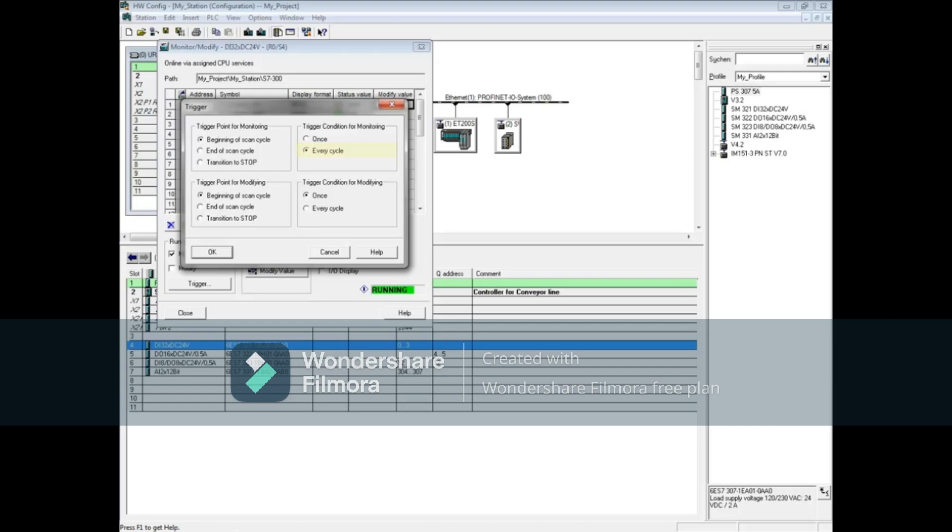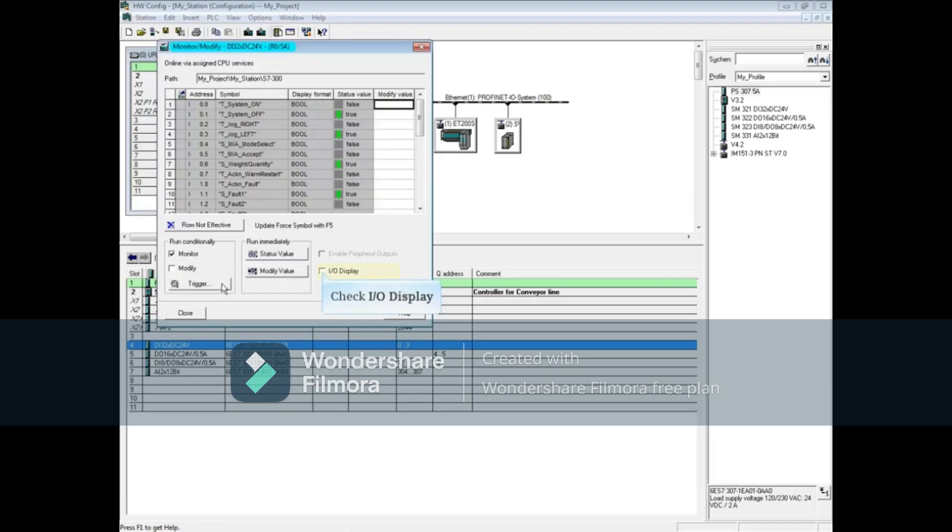You may also choose to monitor at the end of the scan cycle, which would be better for outputs. And lastly, you can monitor when the CPU transitions to stop. If you change the trigger condition to once, then when you check the monitor box, updating will only occur for one cycle instead of every cycle.